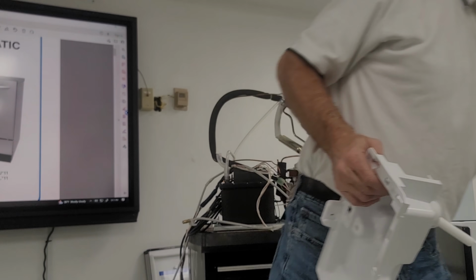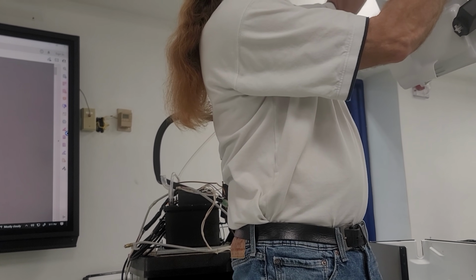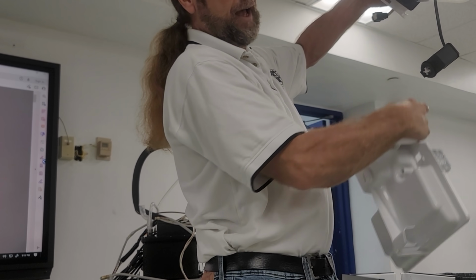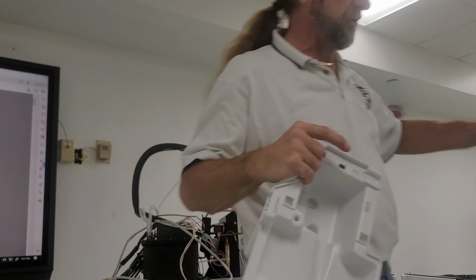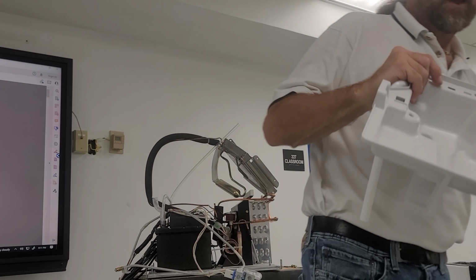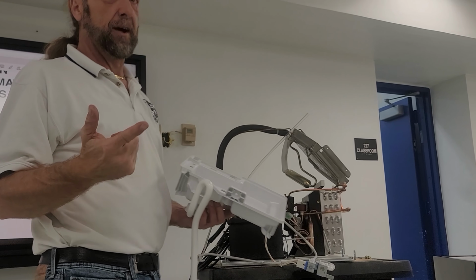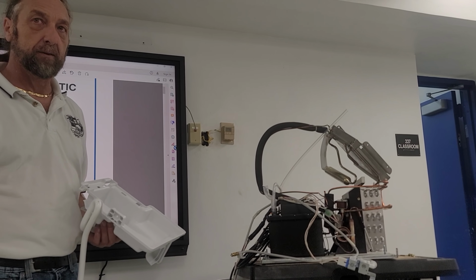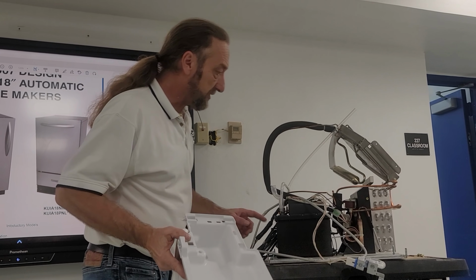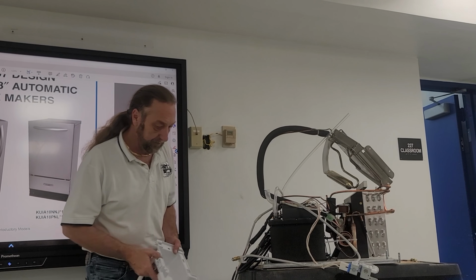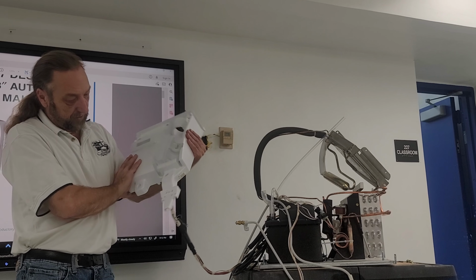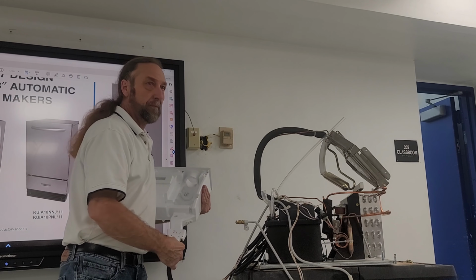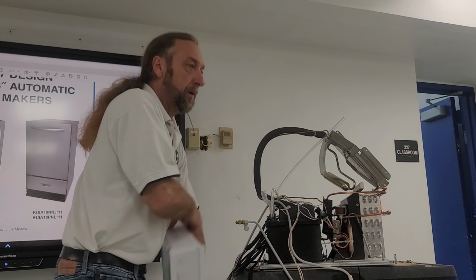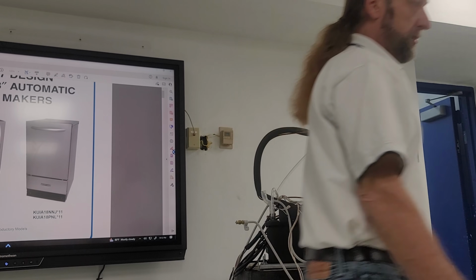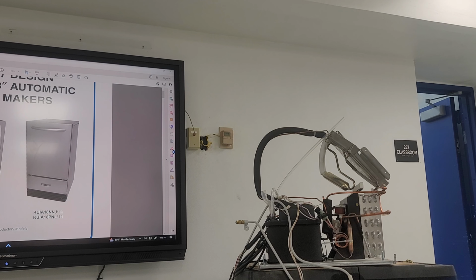I would see it probably mounted right in this opening here or in that opening there, and it would go down into the water level on our recirculation pump. So how does this one know when to drop the ice? I said the old ones drop the ice by what? Time. No, by the suction line evaporator thermistor. The evaporator thermistor has to be somewhere up here. Is it on the table? This is a bin thermistor. And the evaporator thermistor is not connected here. I unclipped it. I just don't know where we set it down.